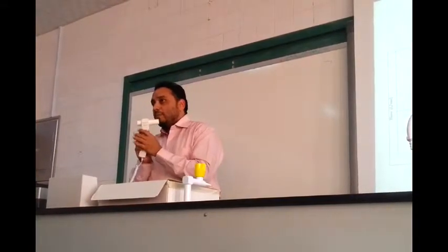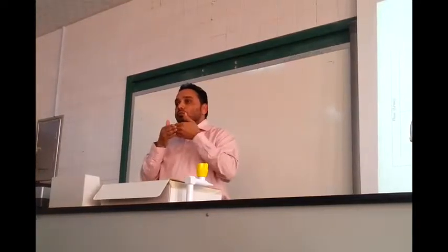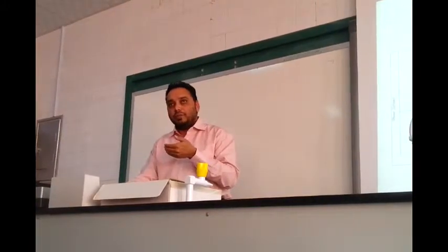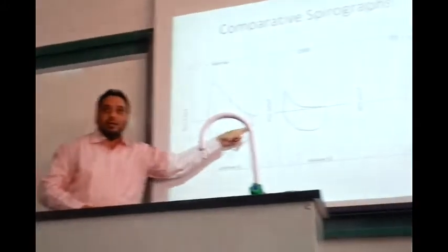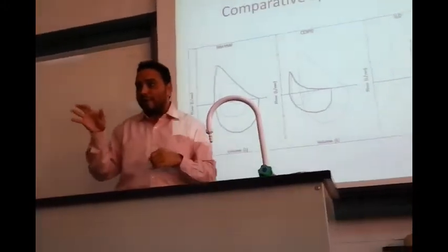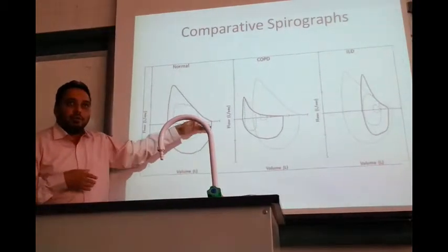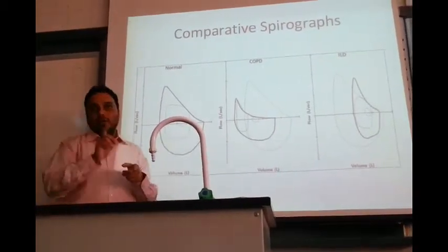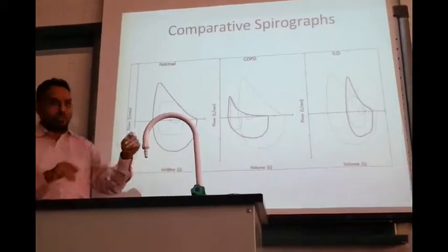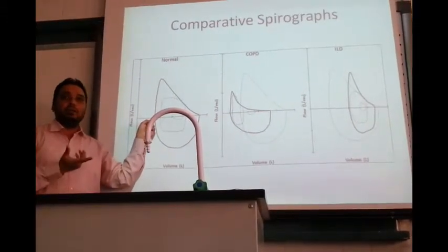After that, when you take in air, the membrane will move towards you, towards your mouth, isn't it? Inside the machine. Electronically, the machine is recording that. So movement of the membrane is towards the person. The membrane goes down, it records a negative deflection as compared to the baseline. As his inspiration is complete, it comes back to the baseline.